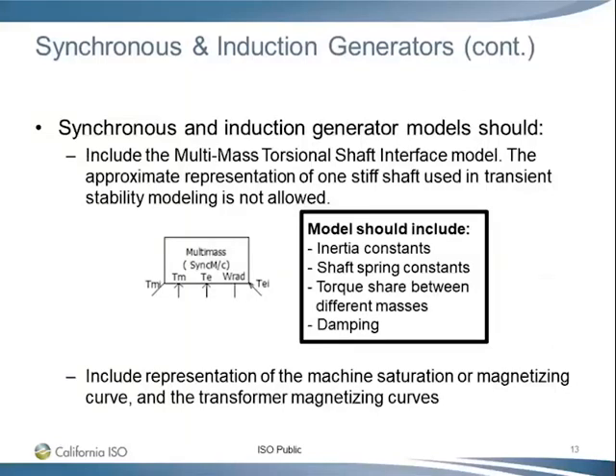So what do you need to submit? It's similar to the dynamic model, but in addition to the regular dynamic model, the generator model, exciter, governor, PSS, you need to include a multi-mass torsional shaft interface model. So this is the model that's in addition to the regular dynamic model. This must be included. This is required for SSR type of study. Also include the machine saturation and the magnetizing curve. Next slide.